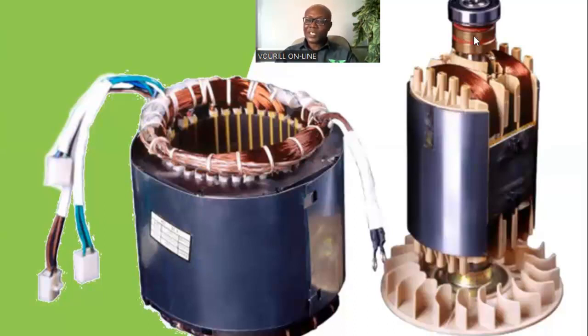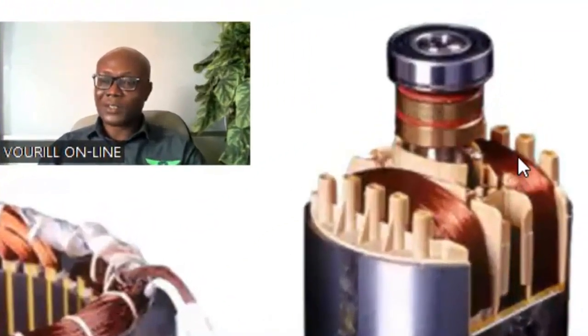So these are slip rings. If you look at these two windings, you see that they are insulated from the ground or the rotor itself, the yoke of the rotor. They don't have any business with the yoke of the rotor. So you can test continuity to ground. Then the finish, you can either connect finish to finish and start to start, or finish to start. The finish lead from this winding and the finish lead from this winding are taken to these two terminals, connected to slip ring 1 and slip ring 2. Some connect them finish to start. It depends on the generator configuration.